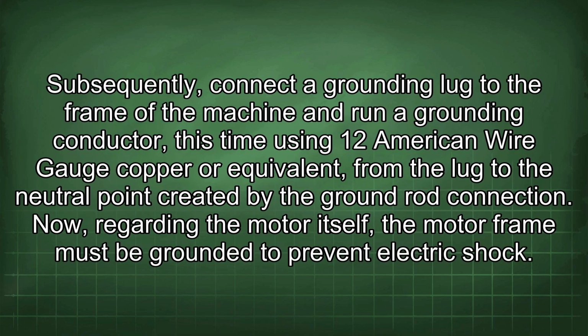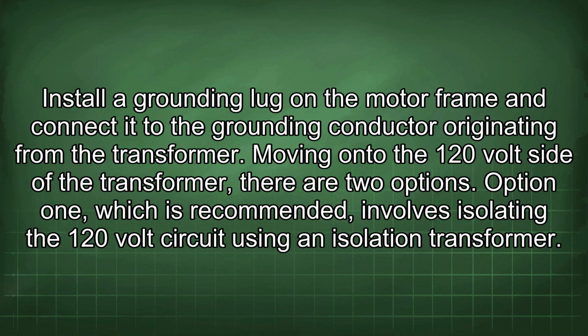Subsequently, connect a grounding lug to the frame of the machine and run a grounding conductor, this time using 12 American wire gauge copper or equivalent, from the lug to the neutral point created by the ground rod connection. Now, regarding the motor itself, the motor frame must be grounded to prevent electric shock. Install a grounding lug on the motor frame and connect it to the grounding conductor originating from the transformer.